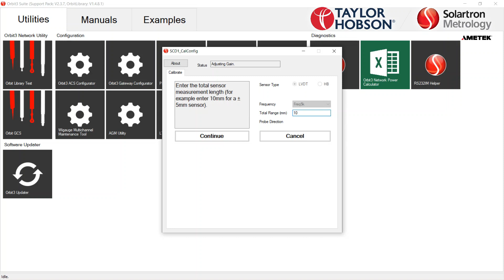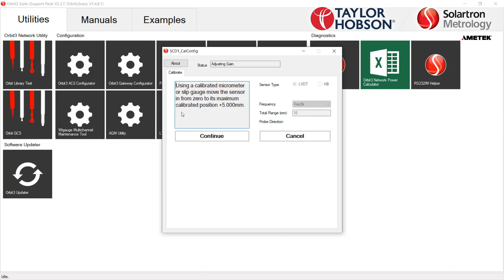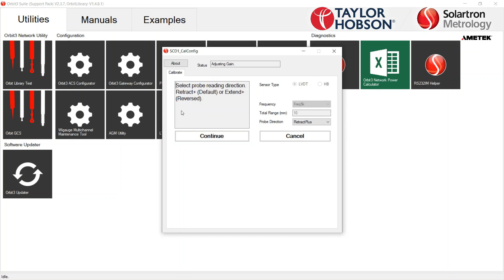Now the next step, using a calibrated micrometer or similar, like a slip gauge, now you start to move it the rest of its range, to its maximum calibrated position, which in this case will be plus 5 millimeters. Now then you select the probe reading direction, and now the sensor is calibrated.